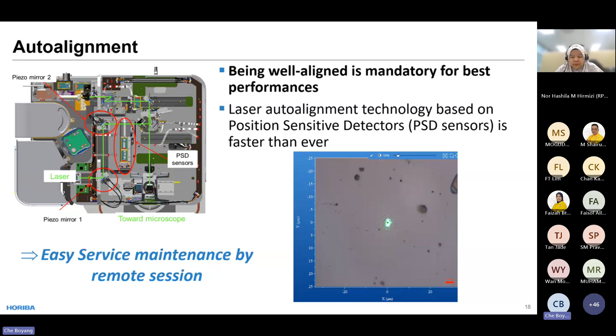To do the auto alignment, the user just needs to click the button in the software, and the software will run the auto alignment automatically for the user. Within 10 to 15 seconds, it will align the system and move this laser spot back. You can see the animation here, and it gives you better alignment. With this feature, the user will be able to ensure the instrument is always in good condition before their measurement.